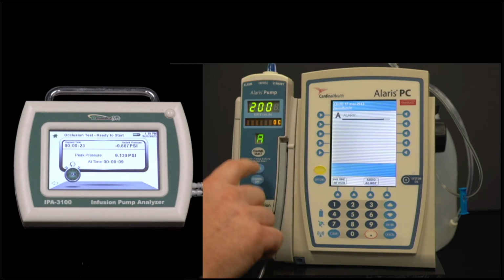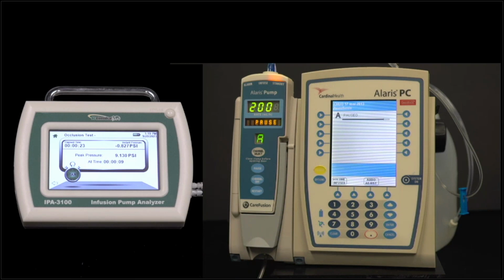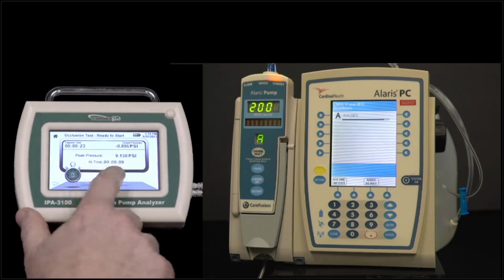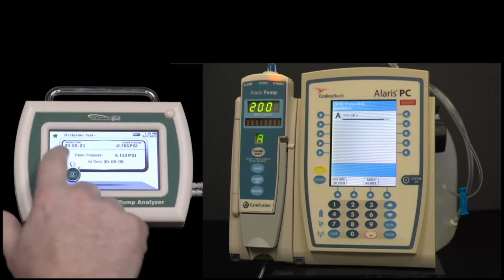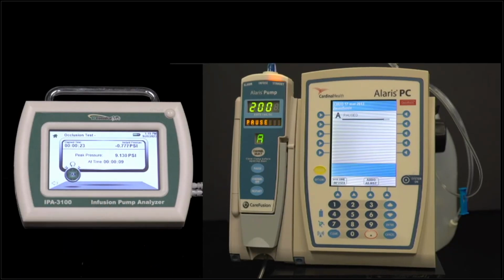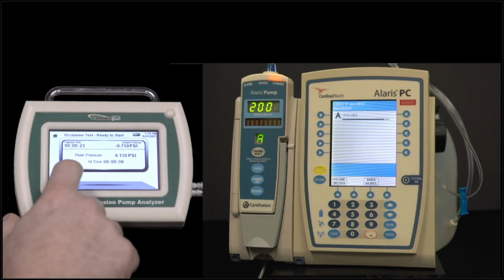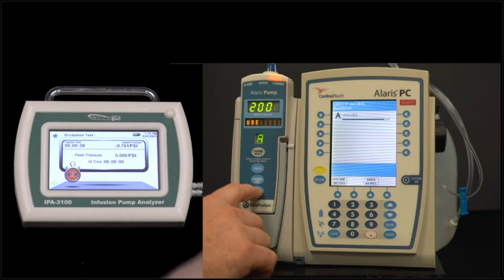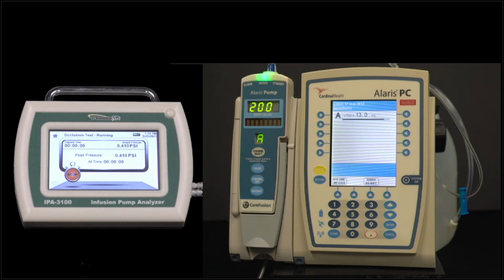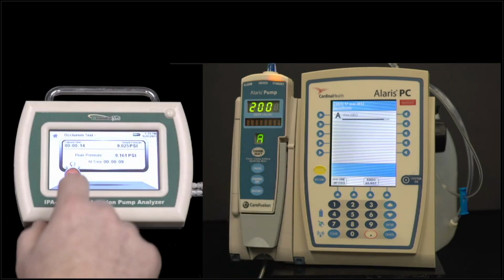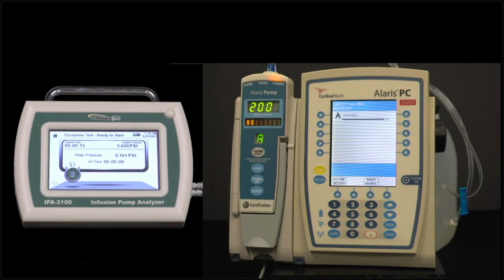And now in order to get this to stop yelling at me, I'll just hit the pause button. So we get the peak pressure, we get what time the peak occurred, and then the elapsed time for the total test. And now it's ready to run another test. We can run another one if we wanted to, start a new one here, and we restart the pump, and we can see what kind of consistency we have there. And again, we can compare that against the service manual for our pump and make sure that it's performing like it should. So those are quick and easy tests that we can run.